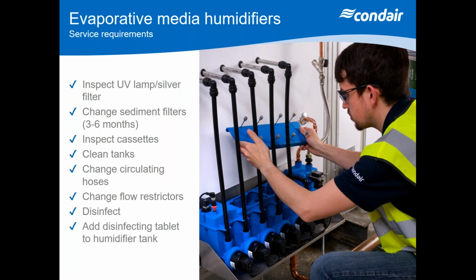And then we'll also periodically change the UV lamps on these systems. Now, the UV lamps can be either a direct UV for the water incoming supply, or you can also now have submersible UVs and recirculating UVs. But generally, to make them as effective as possible, we recommend that UVs are replaced annually, because the UV rays will deteriorate over a period of time. And also the quartz sleeves, if they haven't got a sediment filter in front of them, will actually cloud up and not give you the full extent of the UV rays on the water, which can kill off the bacteria.